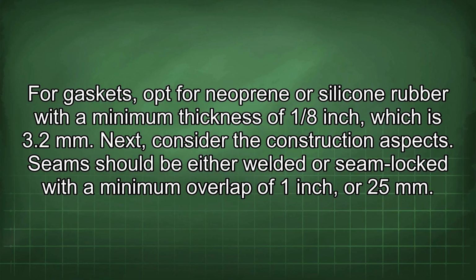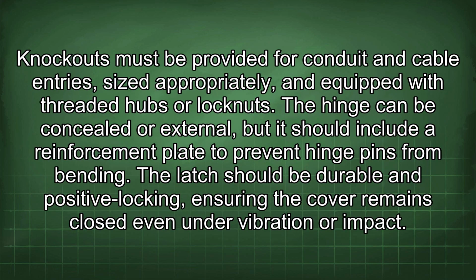Seams should be either welded or seam-locked with a minimum overlap of 1 inch or 25 mm. Knockouts must be provided for conduit and cable entries sized appropriately and equipped with threaded hubs or lock nuts. The hinge can be concealed or external, but it should include a reinforcement plate to prevent hinge pins from bending. The latch should be durable and positive locking, ensuring the cover remains closed even under vibration or impact.